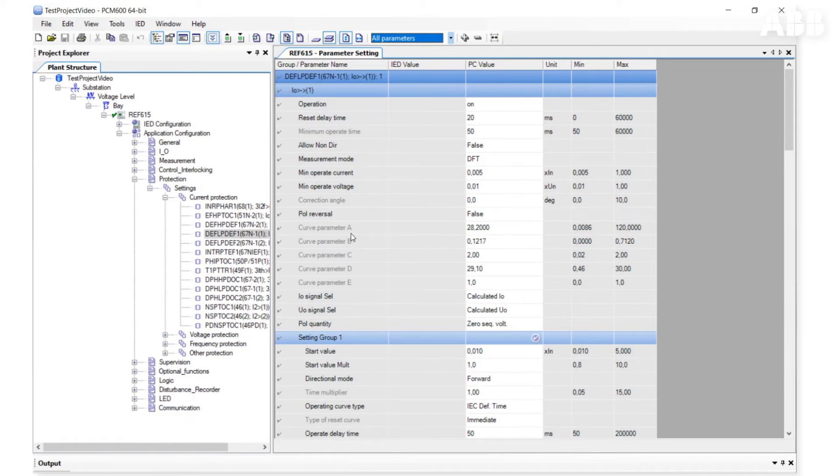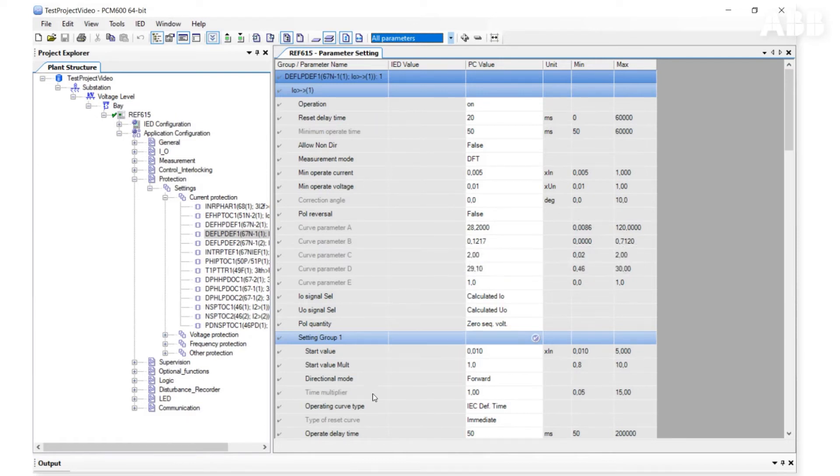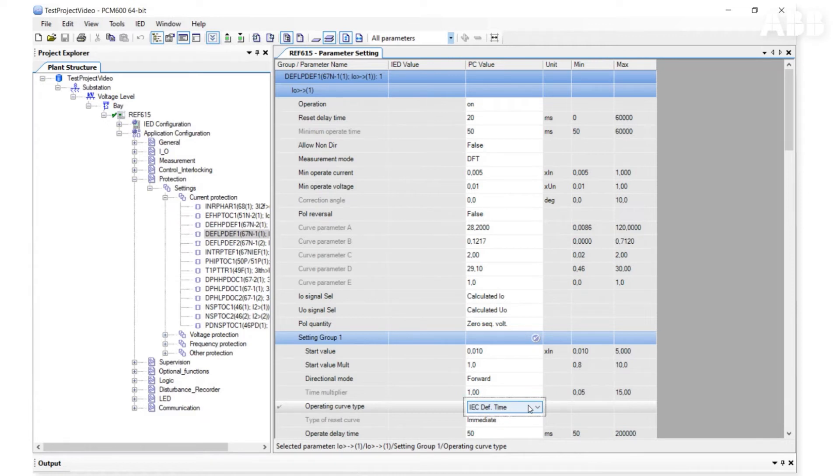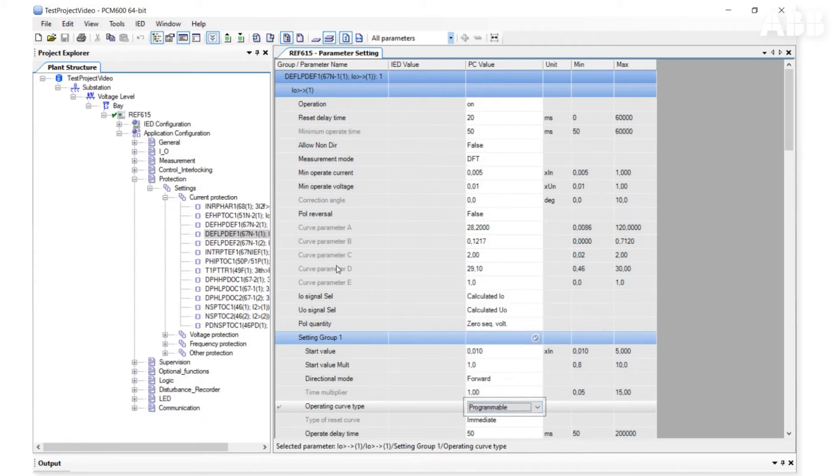In the current example, all curve-related parameters are gray because operating curve type is IEC definite time. If we change it to Programmable, all curve parameters will be active.